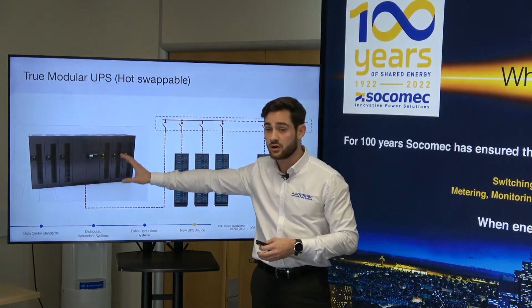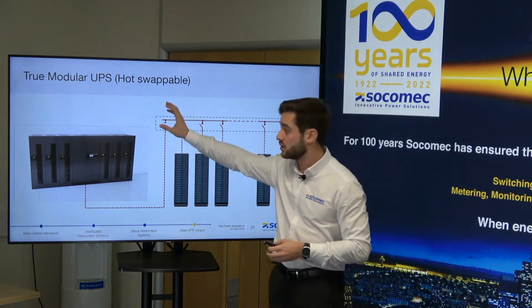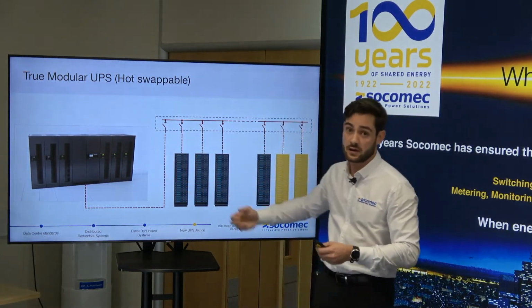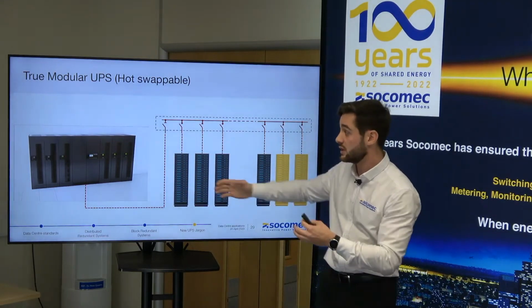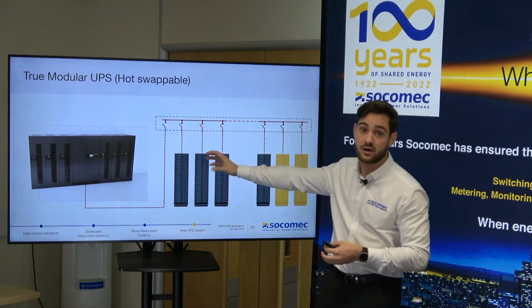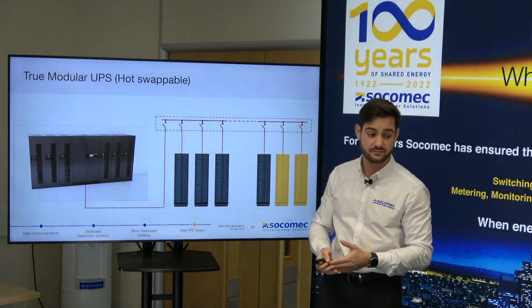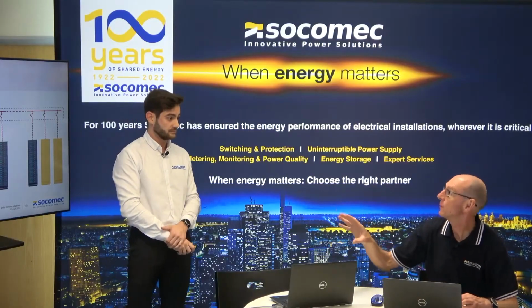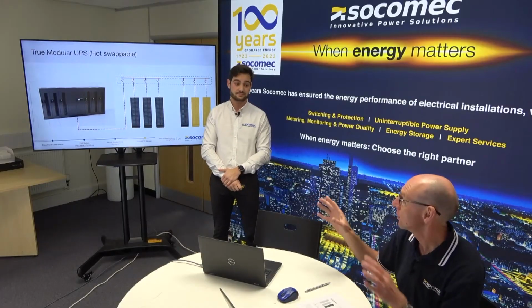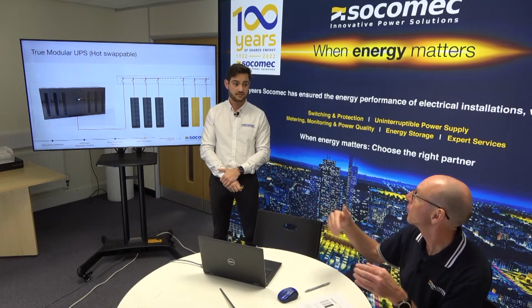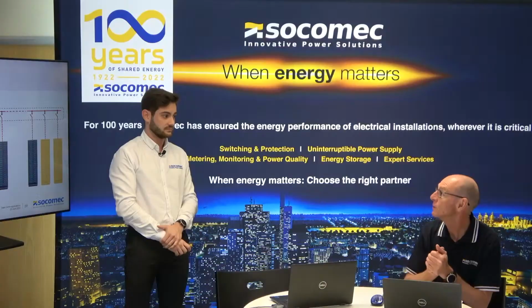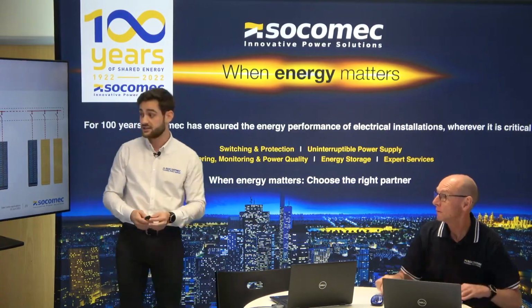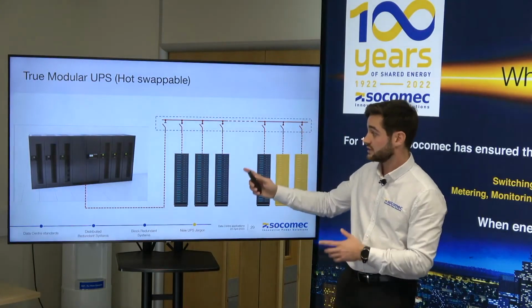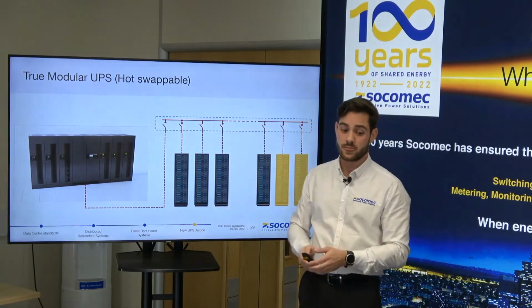So with your online double conversion, if there is a failure of power voltage while you're fitting a new module, there is no problem because the UPS can take the load on the batteries. Obviously, the key point is the power slots have to be installed at day one, so you size the power slots for your end of life, or your expected end load, and then you can add the power modules as you need to. Yes, totally right, for the installation, absolutely. So that's for a modular UPS system, power module.